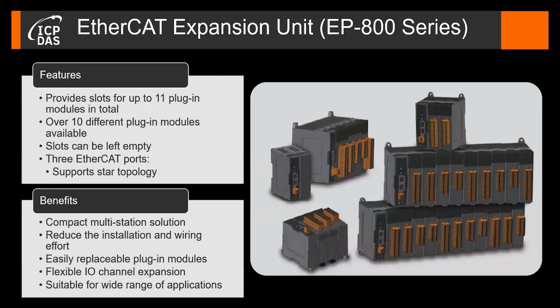The EP800 series is our EtherCAT I/O expansion module. The trend in the industry is to increase the compactness of the machine plant and reduce the cabinet size. So the purpose of the EP800 expansion device is to combine several distributed slaves into one compact unit to reduce the required cabinet space. The EP800 is basically a compact multi-station solution. You can choose chassis with 1, 2, 3, 5, 9, up to 11 slots. Slots can be left empty. The empty slots can be used for future machine extension.